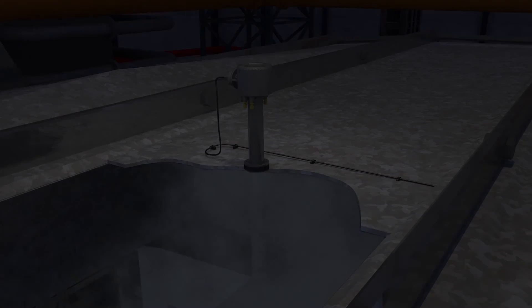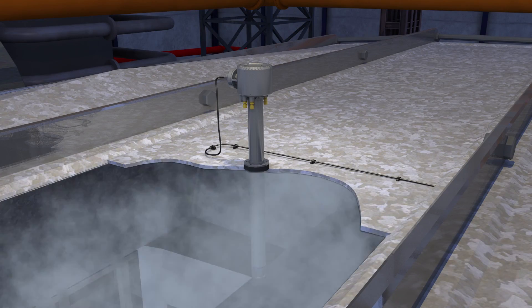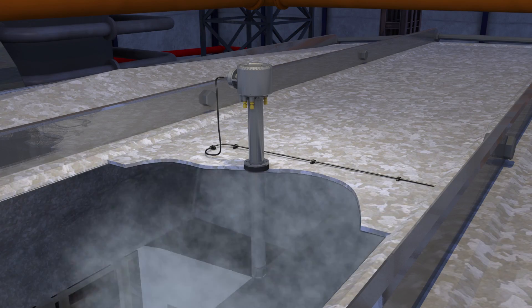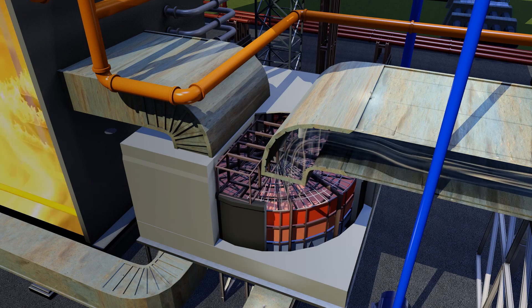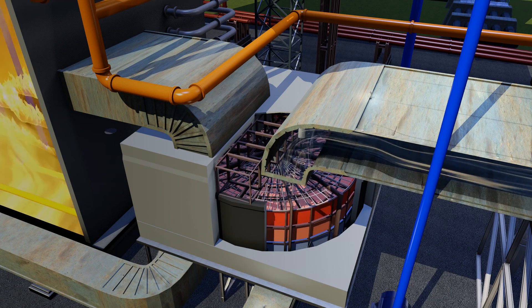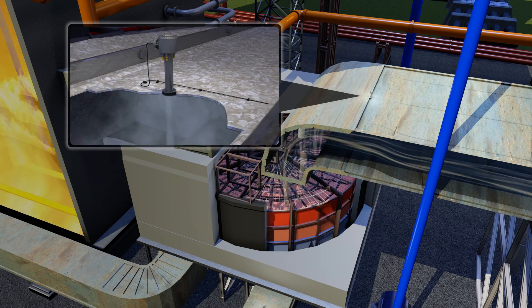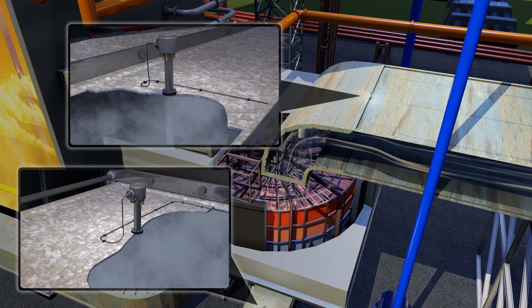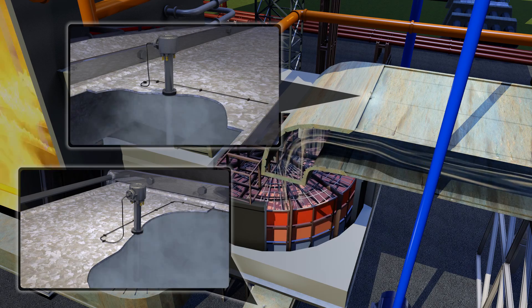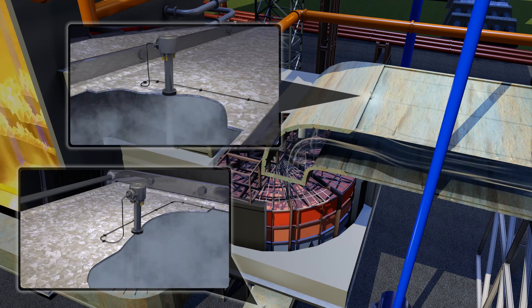Zirconia oxygen probes can play a key role in helping to quantify air leakage. By measuring and comparing excess oxygen levels at the entrance and exit of the air heater flue gas stream, the probes can help operators to assess air heater performance.